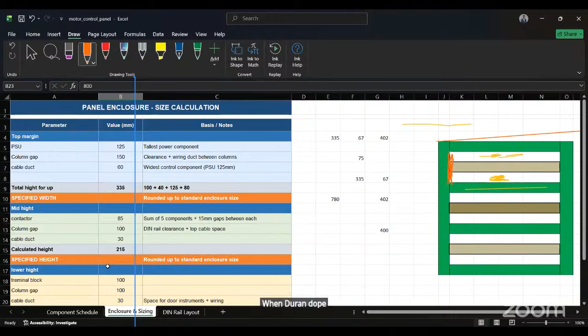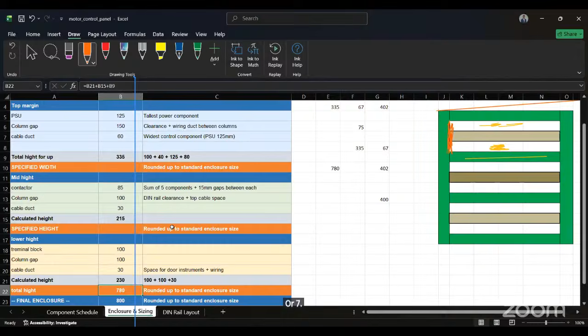On the roundup, I said our total calculation was 780 — that's 780 if you add this plus this plus this. But we don't round down in panel building; round down means going for 750 or 730, but instead we round up to the closest whole number. So we go with 800, and that's why we chose 800 for the height of the panel.